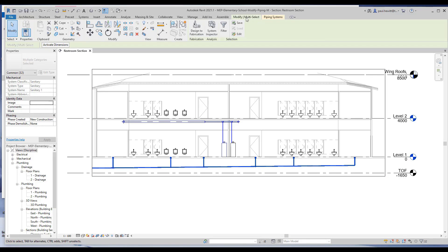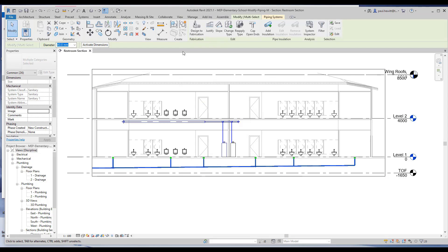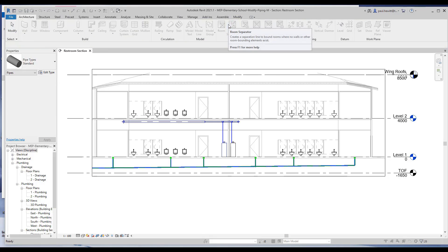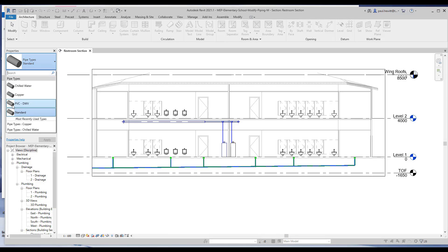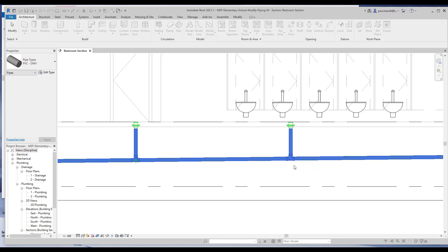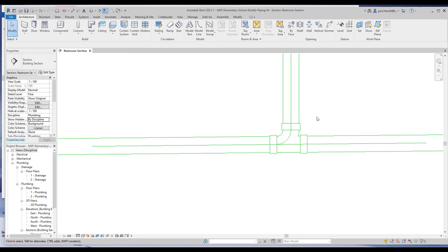This will allow us then to go and change the type. But as you can see, we'll need to filter out the floor drains, so the plumbing fixtures we don't want. Now you'll see the ribbon changes. So in here we'll see change type. I'm going to remove it from the standard type, and then we're going to change it to the PVC type of piping. And as soon as we've done that, if we zoom in, you'll see the connectors are correct because it's using the correct pipe type.